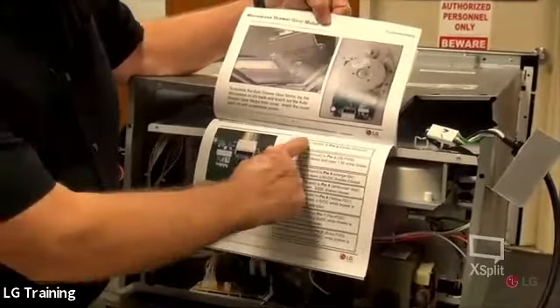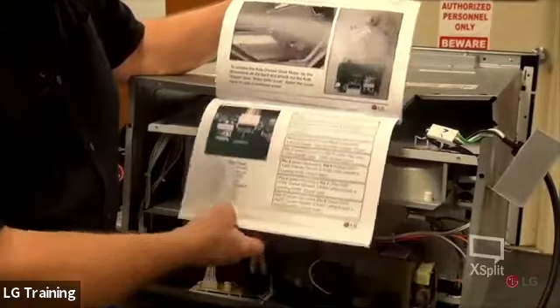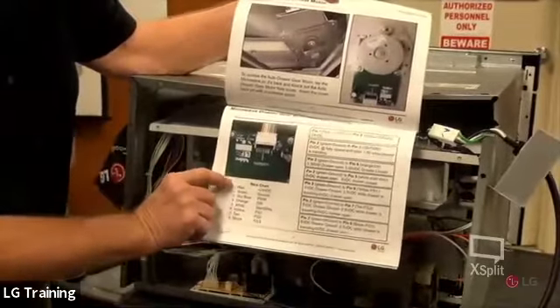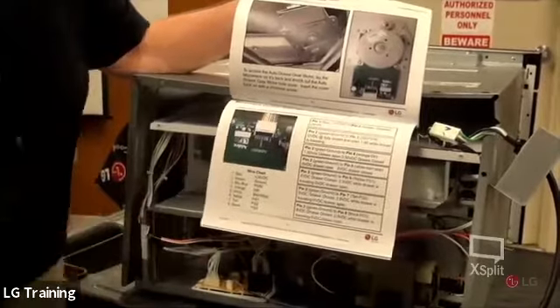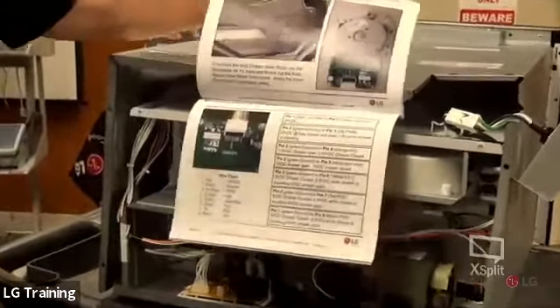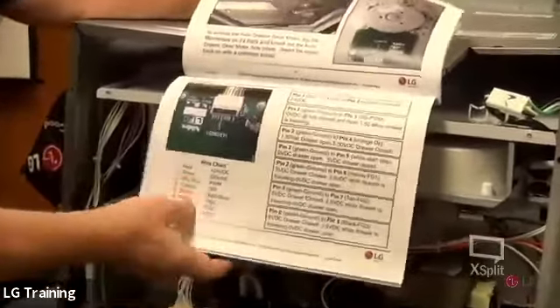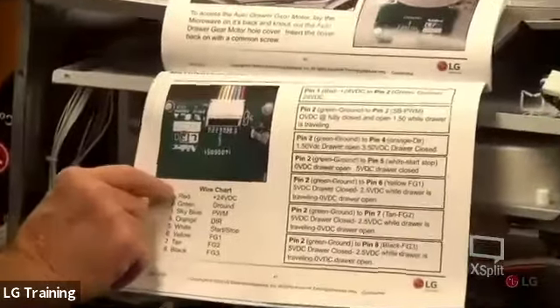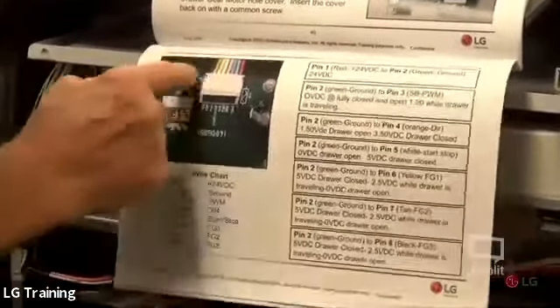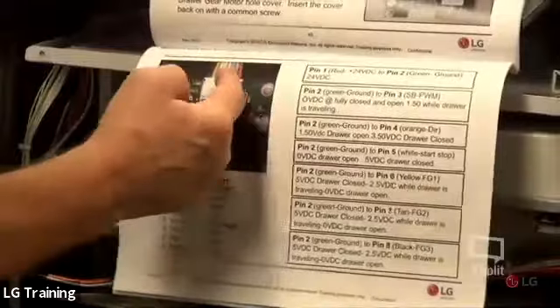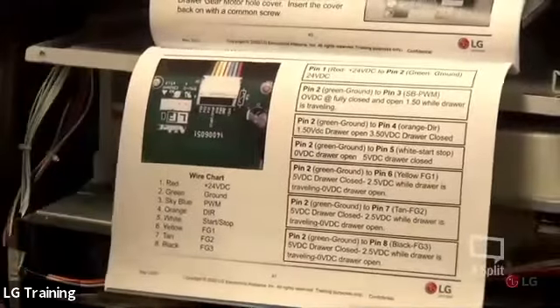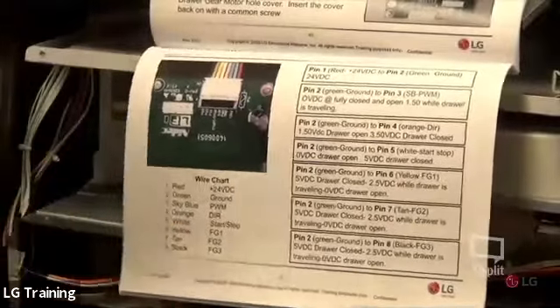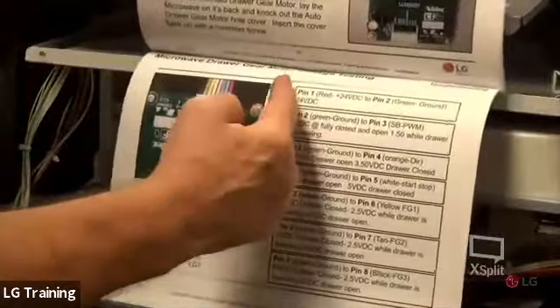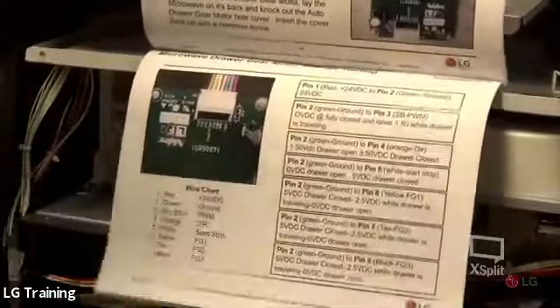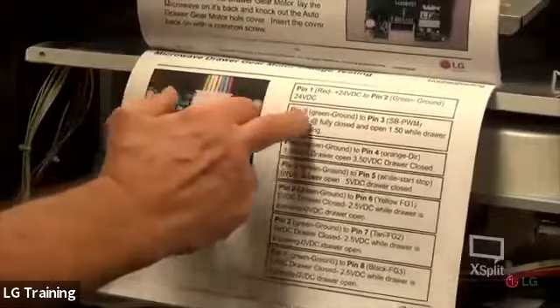I broke all these connections down for you, showing what each pin represents. I told you earlier the first two pins were for the motor voltage, red and green. I had them backwards, I said black and brown, but black and tan is something different. Anyway, we broke them down: pin 1 to 2 is where you check for that 24 volts, and pin 2 is your ground.